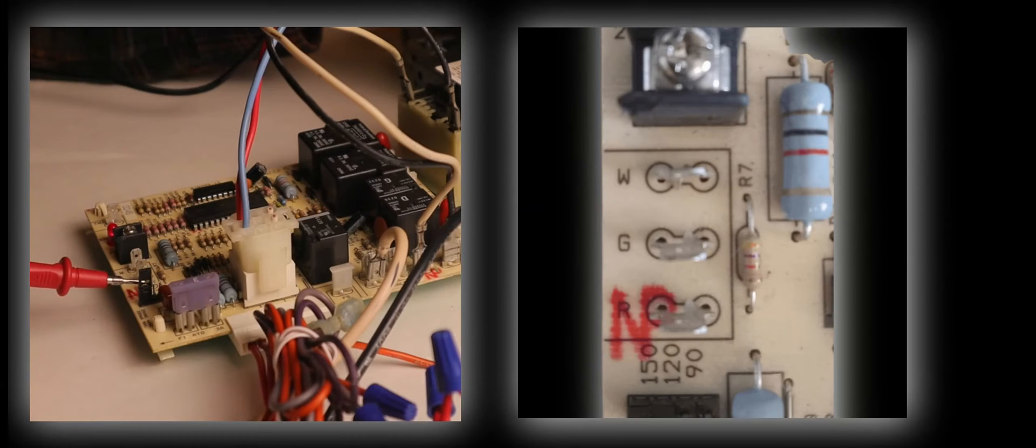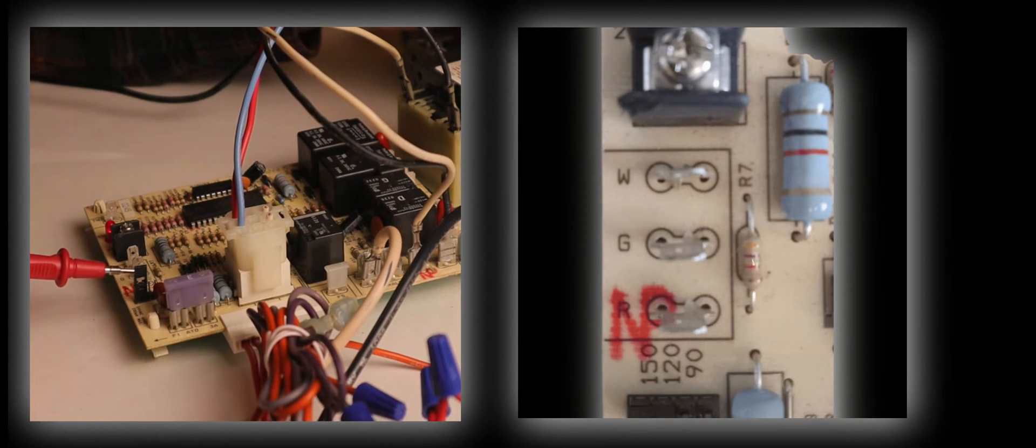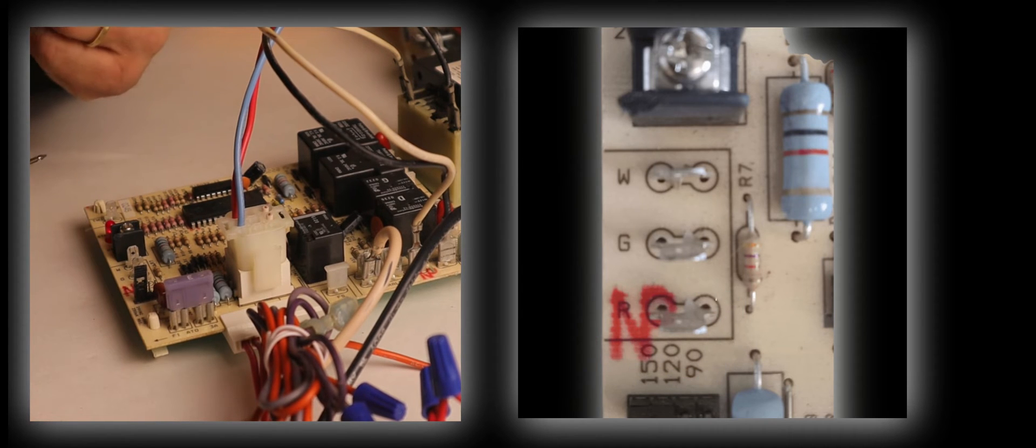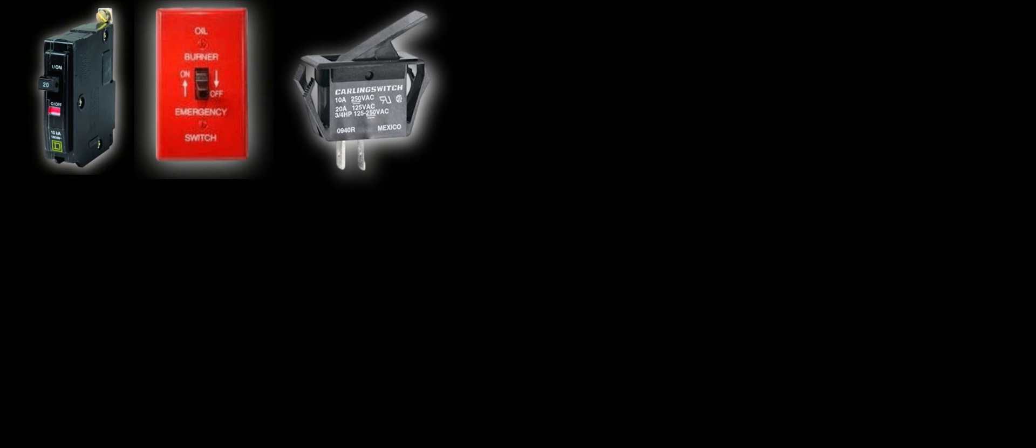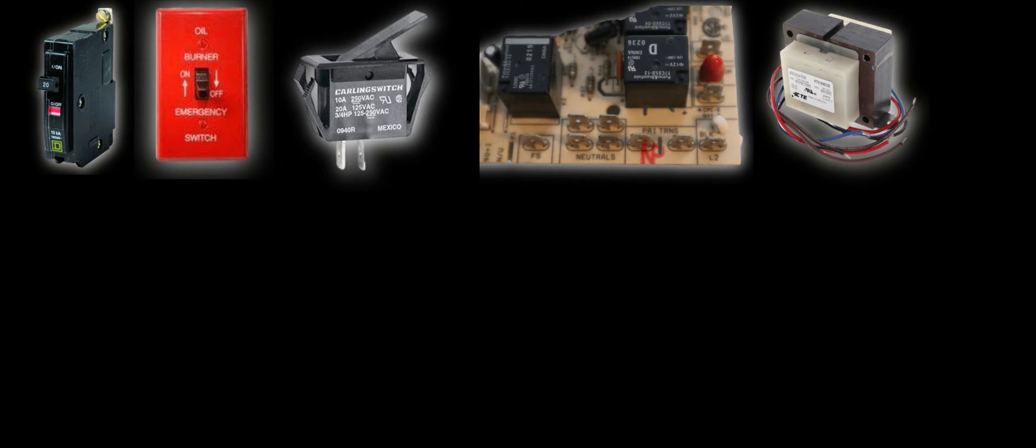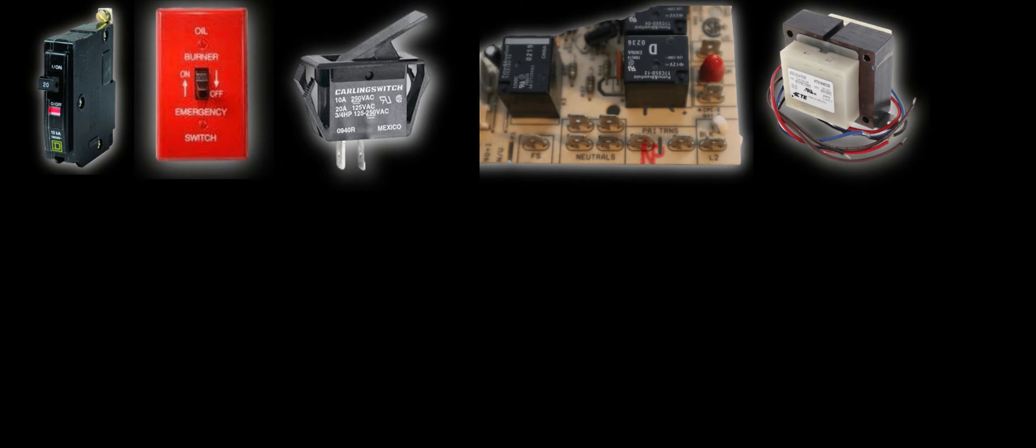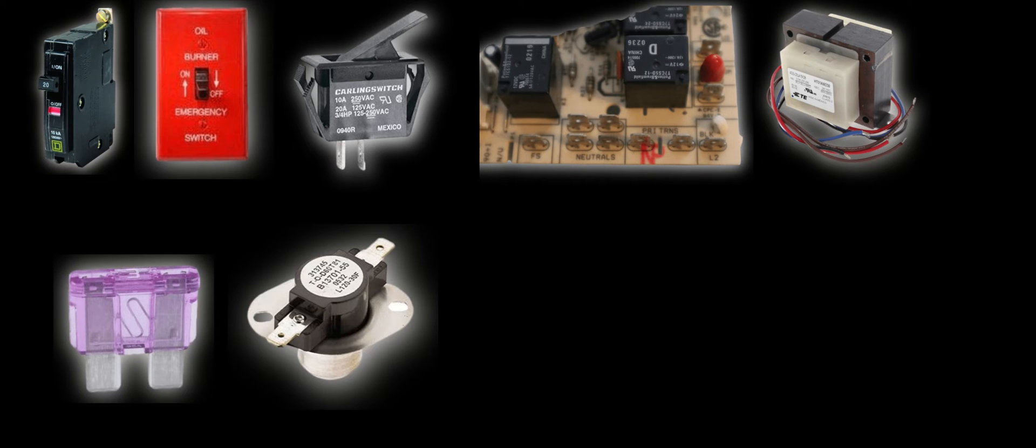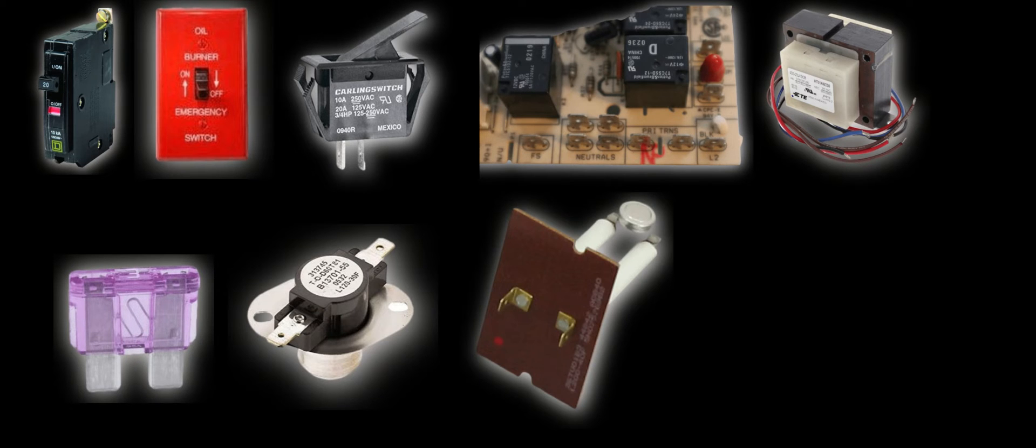The next place I find power is on the R terminal where I get my 27 volts. This is where the thermostat wiring gets hooked in. So burner switch, door switch, control board, primary on the transformer, secondary on the transformer, fuse goes to our fan limit switch, the high limit switch, and now finally to our R terminal. Let's wire in a thermostat.